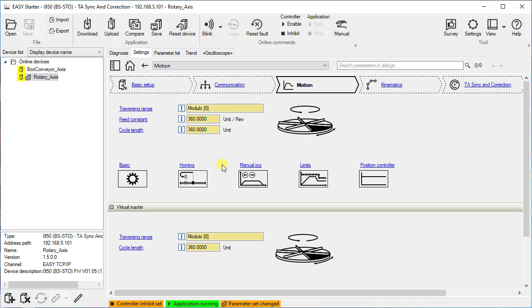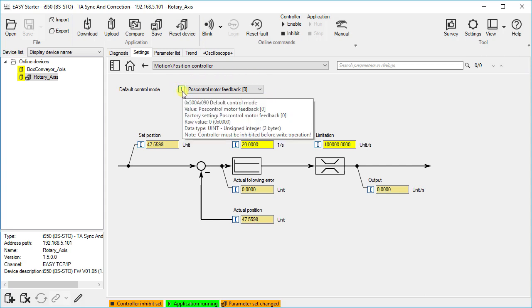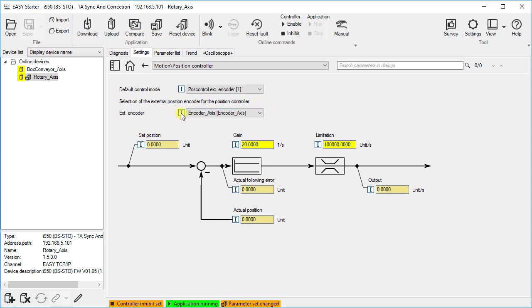We will now skip the manual jog in the real axis, because we will use this function from the virtual master. The limits are important in the case of a limited traversing range or in the context of extended safety engineering when monitoring limited axis movements. For our application we go to the interface position controller. Here we can determine whether an additional external encoder, which can be optionally connected to the encoder module slot B, is used. It is important that in this case not only the control mode is switched to external encoder via index 0x500A:90, but also the position controller for the external encoder is activated via index 0x500A:92. In our case we use the motor encoder for position control.